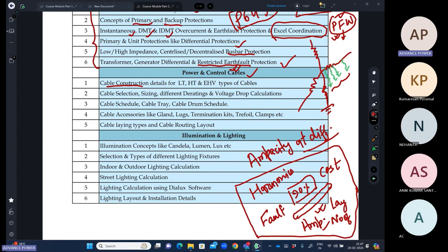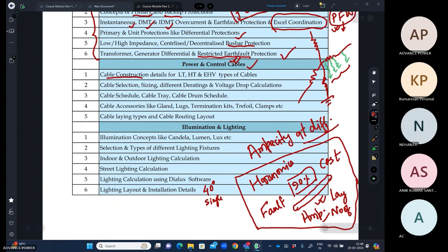A cable is manufactured based on some basic assumptions. If I tell you, it is designed at 40 degrees C air temperature, and as a single cable running with no other cables with it. That is when I'm talking about the air, cable laid through the air. When a cable is laid through the ground, some more parameters come in, like 30 degrees, and it is designed for single laying.